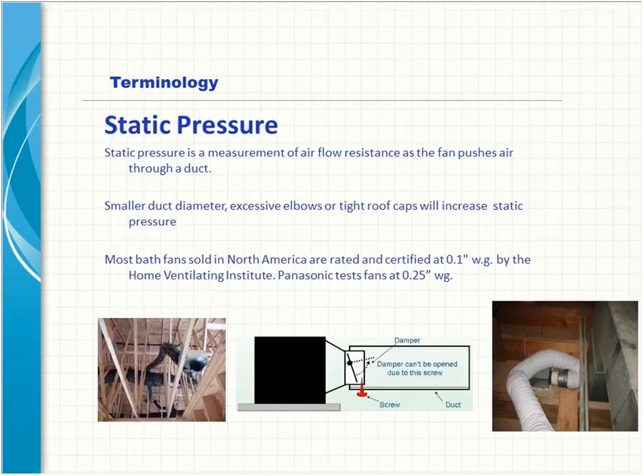we want to always try and reduce the amount of static pressure by reducing the number of elbows, keeping the runs nice and short, and making sure that they're terminated to the outside, but with a termination that doesn't cause too much resistance. And then it's not uncommon also, during the install, you need to fasten the ductwork to the unit. Has anybody ever seen an install like the middle picture here, where the damper is pinned shut by the screws that are installed to hold the ductwork on?